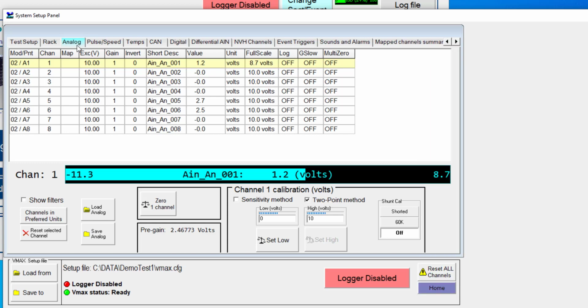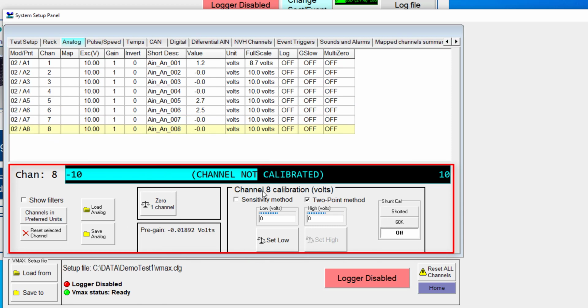So to begin, we're going to talk here about the 4010 analog input module that has excitation capabilities. Now, in our previous video, I did show how we can set our default excitation voltage to a different level. I currently have it set to 10 volts, and I can change this on a channel by channel basis. Also important to note, each analog input module has a maximum of 8 channels per module, and if I did have more than one analog input module, which I do not, we would actually see additional channels go further down inside of this table. But the way the layout works is that you have this table with all 8 channels, and you can simply click back and forth through these here, and then down at the bottom of the screen is where you'll actually do your calibration and zeroing and things like that.